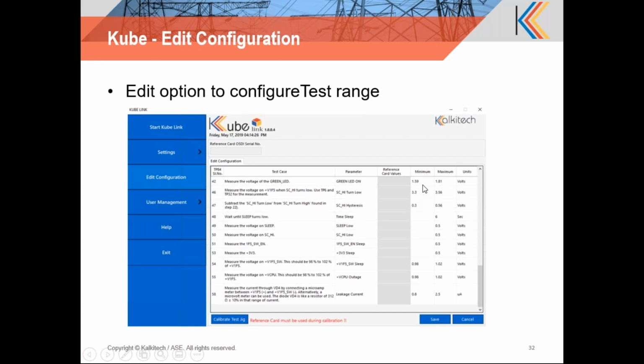Based on that, they can adjust or calibrate the test jig for the minimum and maximum limits, which will later be used as an evaluation for the remaining units under test.